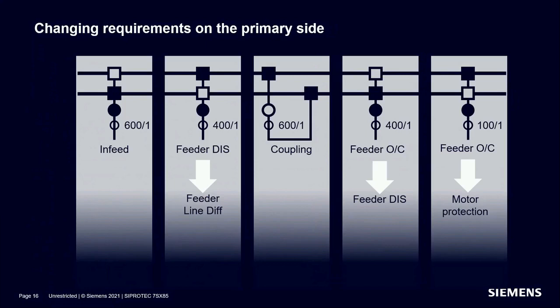Or a feeder is equipped with an overcurrent protection and the network topology changes so that suddenly a distance protection is required. No problem with 7SX85. Another case we often find in industrial plants. Today, the feeder is protected with an overcurrent protection. Tomorrow, the feeder must be connected to a new motor. With the 7SX85, you simply add the dedicated motor protection functions to the existing configuration. The device hardware itself does not need to be replaced.